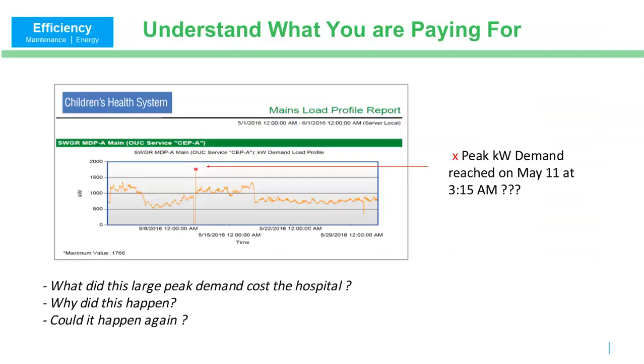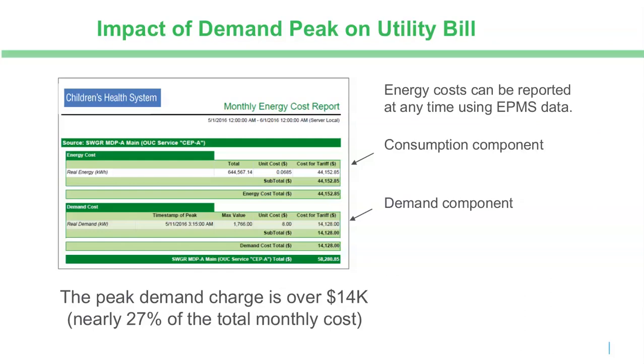So here's an example for demand. This is a real trend from a children's hospital where they experienced a very large peak demand, but it occurred at 3:15 a.m. Obviously, looking at that, you ask: what did this cost us? Why did it happen? And what can we do to make sure it doesn't occur again? With the data and the report from the monitoring system, it's very easy to see the actual demand that was charged. Here we see the demand charge was actually $14,000, about 27% of the monthly spend that month.